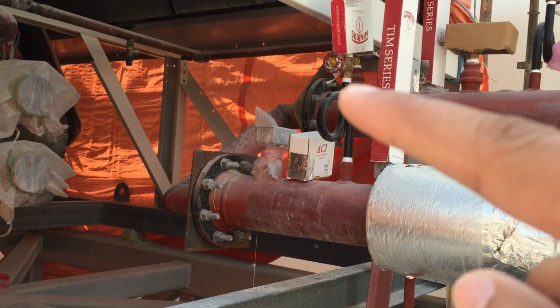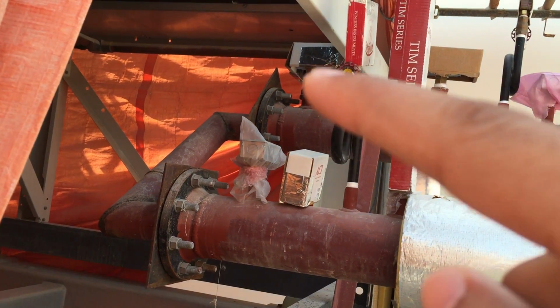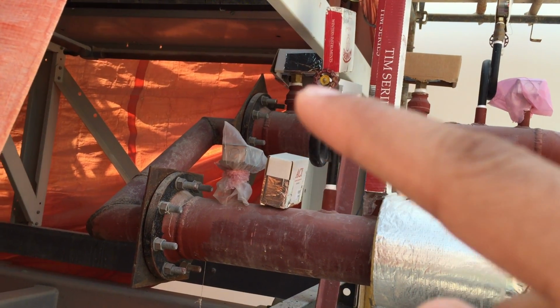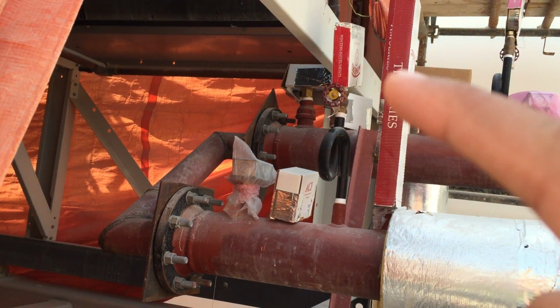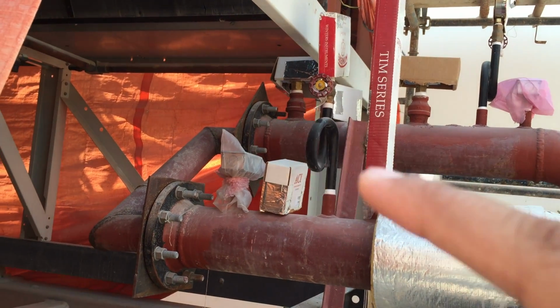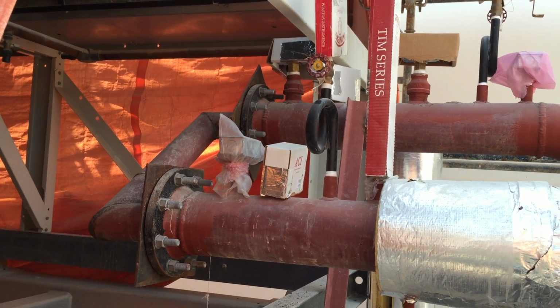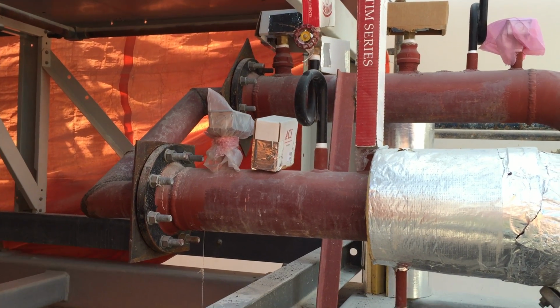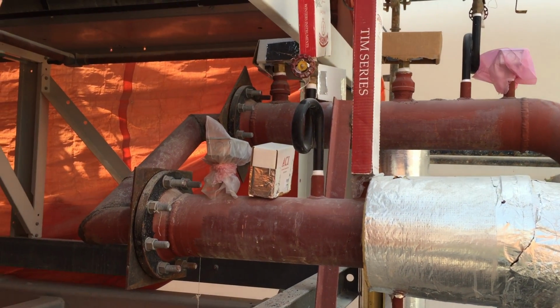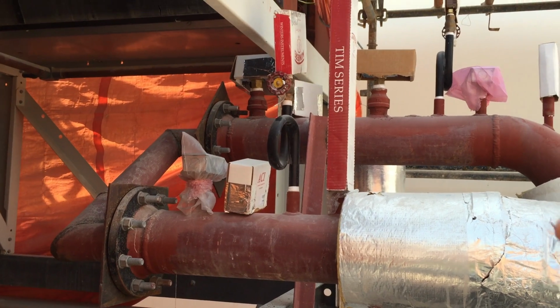So in this piping, first of all we have this flow switch. This flow switch is connected to the chiller control panel. It confirms whether the flow is there or not. If the flow is not there, the chiller will not start. This confirms it.